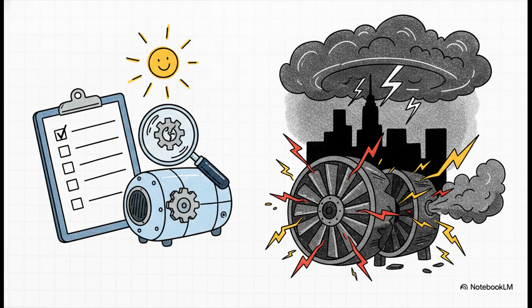You might be tempted to skip these tests when under extreme pressure to get operational, but if you rush the commissioning phase and skip this checklist, you are practically guaranteeing that hidden failure modes will only reveal themselves during an actual emergency. That is exactly when you can least afford a surprise. You want to find out a backup pump doesn't work on a quiet Tuesday morning during a controlled test, not during a massive grid-wide blackout.